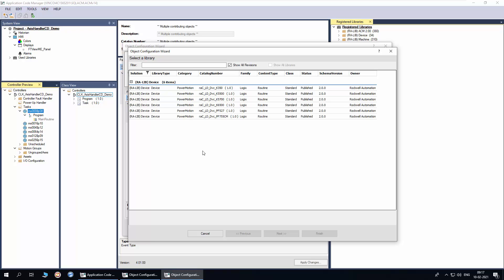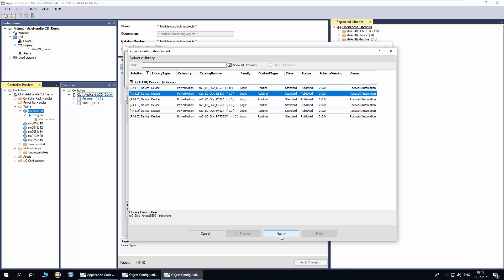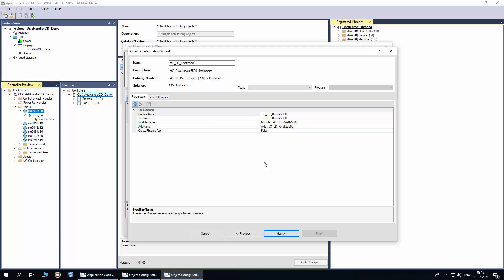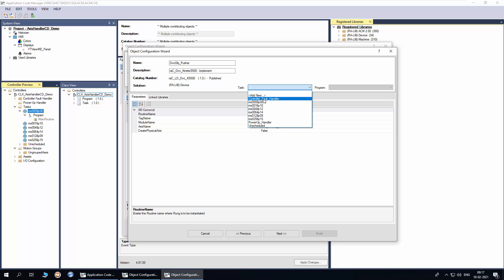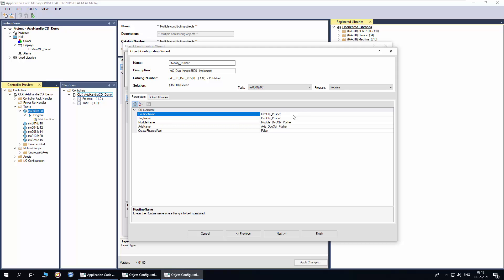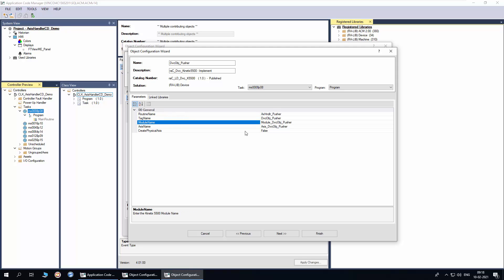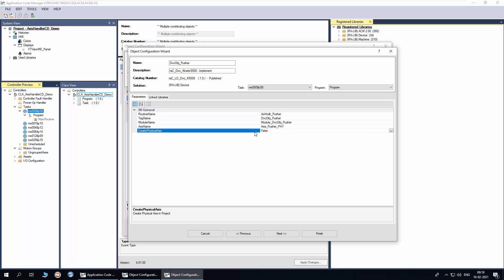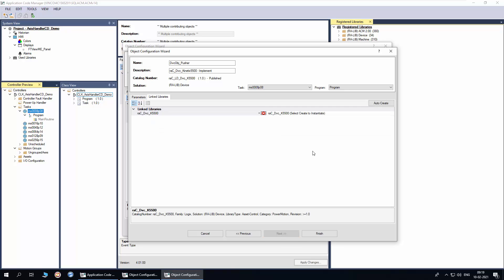These are the available motion device objects. I will select the Kinetix 5500 and click next. I will name the device object instance as device object pusher. Select the task and program. I will enter the same routine name as the handler, so both device object and handler are instantiated into the same routine. This is the hardware module name. I will modify the physical axis name as axis pusher physical. Select true if the physical axis is to be created. Click next. Click auto create to create the link libraries. Click finish.